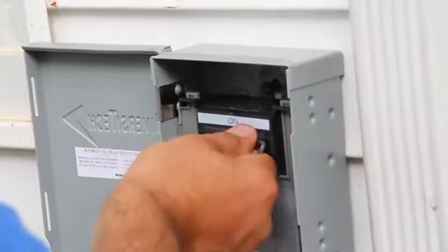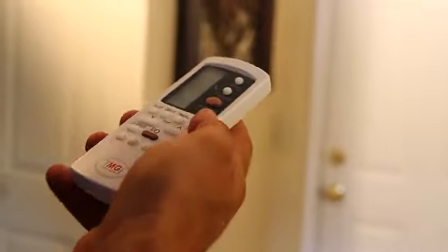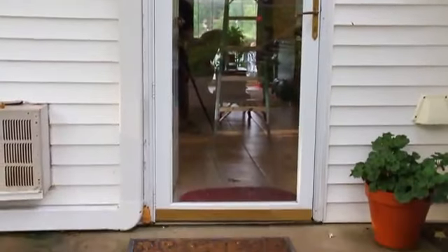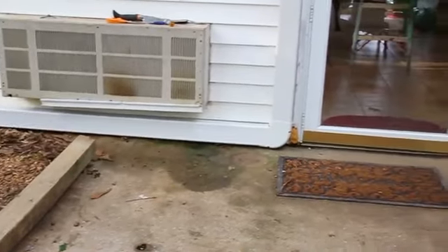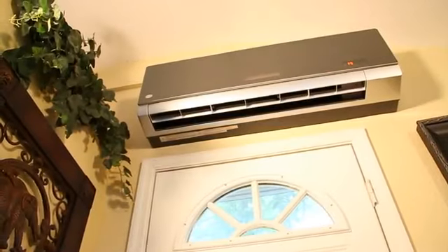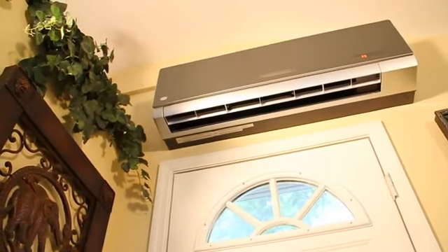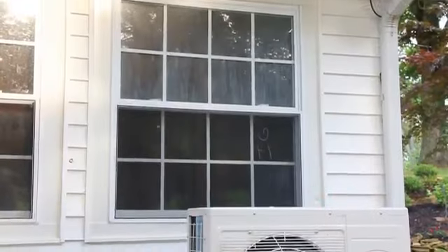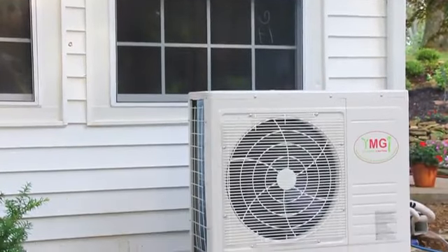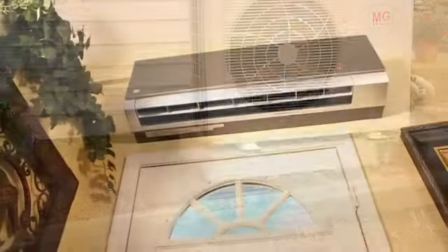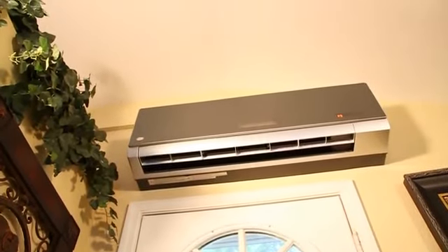It is time for initial startup. Make sure everything is properly connected and grounded according to the installation manual. Double check to make sure. Now, activate the power and move inside. Use the remote control to activate the system. With the system active, it is time to make sure the refrigerant charge is properly balanced. Once that's accomplished in accordance with EPA guidelines, go back inside and set a cooling temperature. With a heat pump, you will also want to check that the unit is also producing the correct amount of heat. With all the pieces of the mini split system installed properly, the unit is now ready to begin sustained operation.